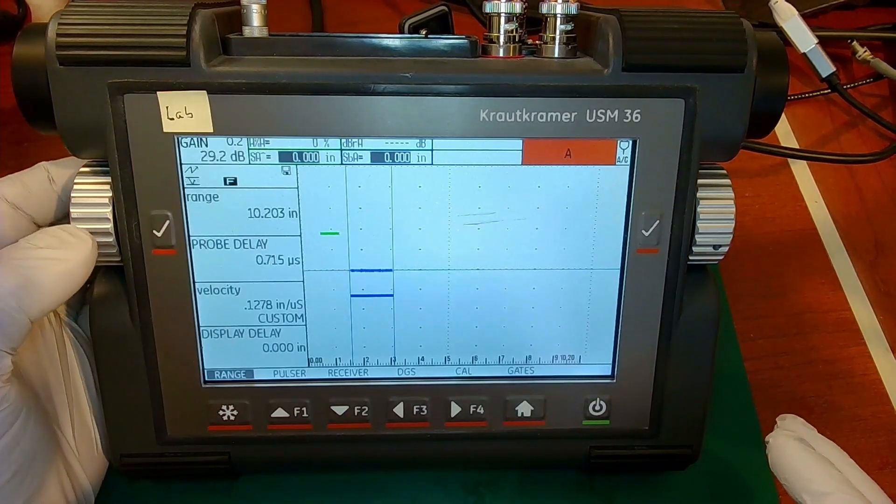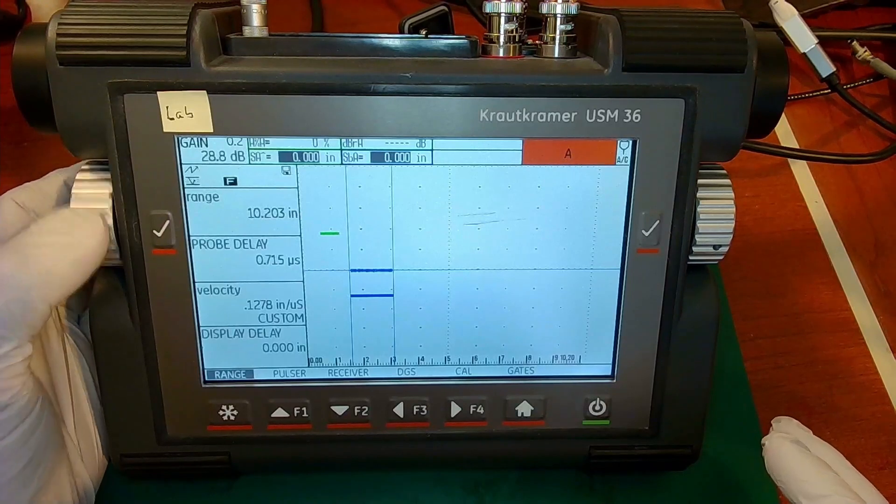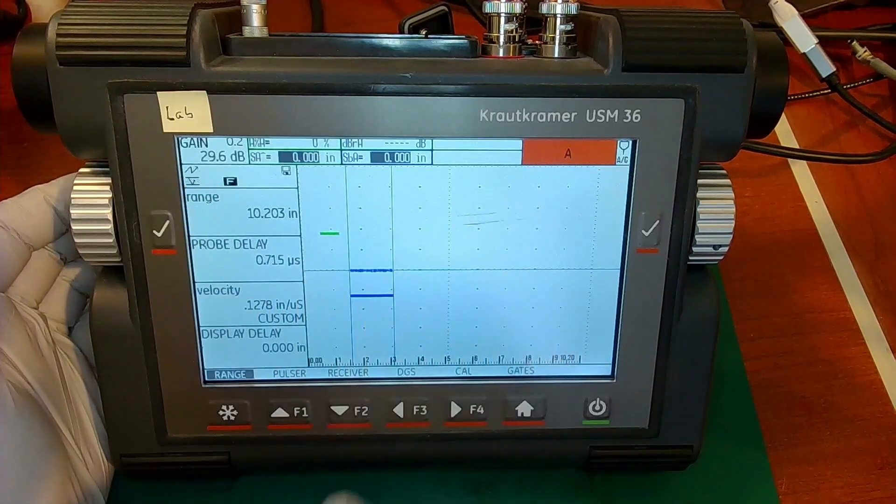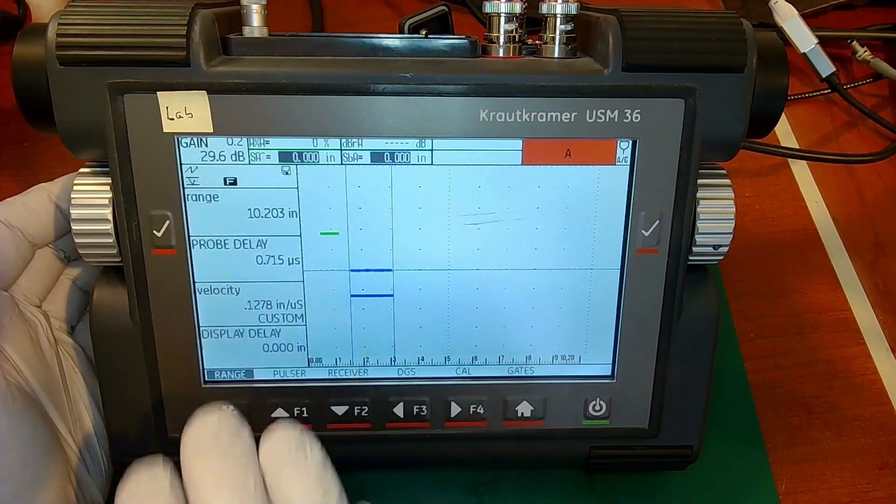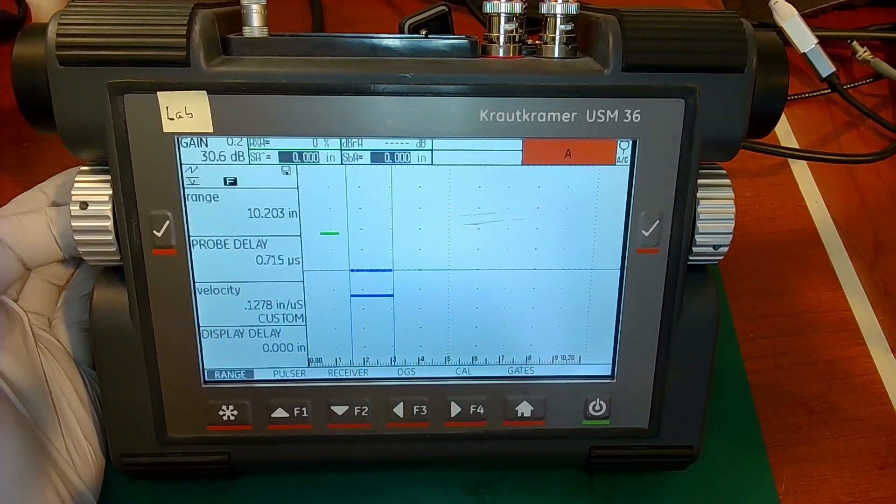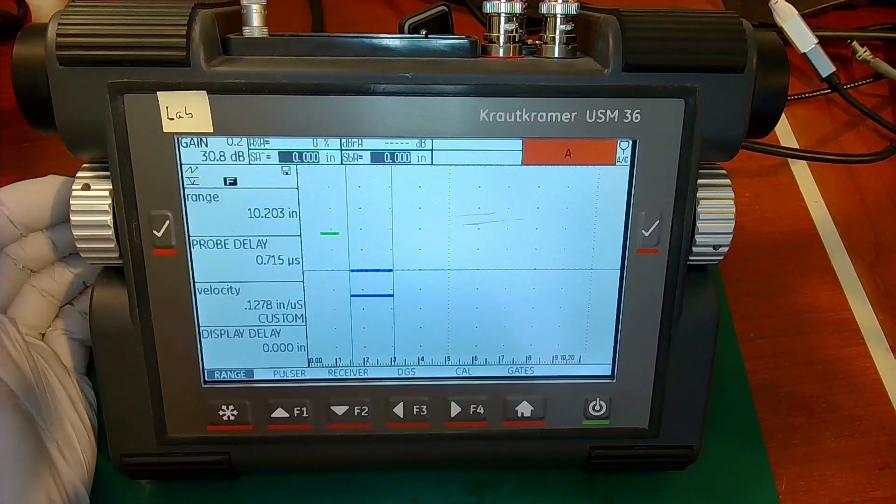Now, as we mentioned, the left knob is permanently assigned to gain. So anytime you're in this mode where you can see the A scan and you have the menus active, the left knob is always your gain control. We don't use that for other things.